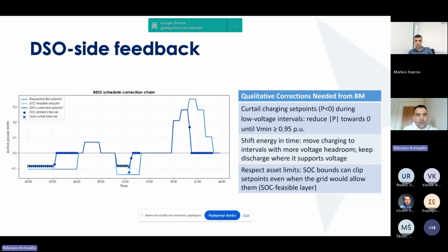So in this slide, you can see some representative corrective actions. The main corrections include the reduction of battery charging during low voltage periods, or the shifting of charging to periods with more voltage margins, while discharge is implemented when and where it can support the grid.